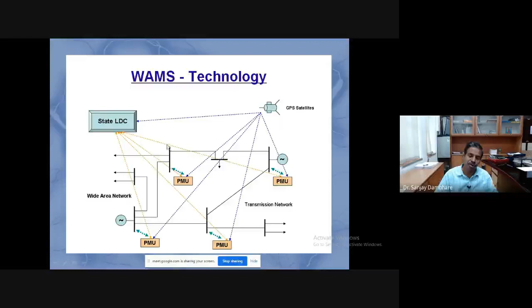So what we can do is conceive a differential relay for the transmission line by using the synchronized data and also the fiber optics. The time synchronization is very important because you can see that a sampling mismatch of even 1 millisecond will lead to about 18 degrees at 50 hertz.